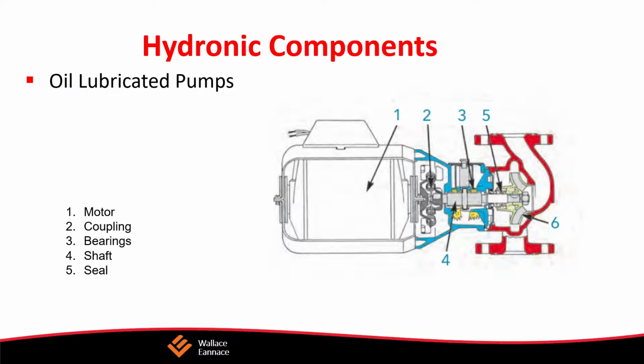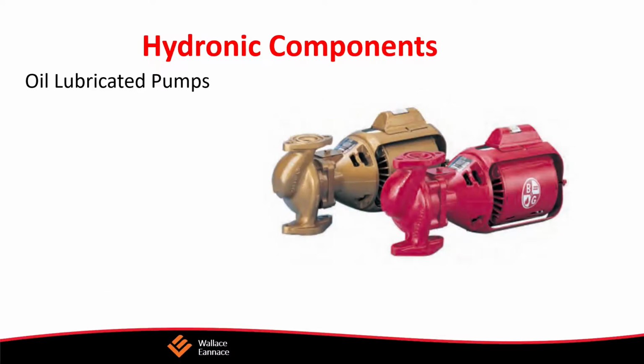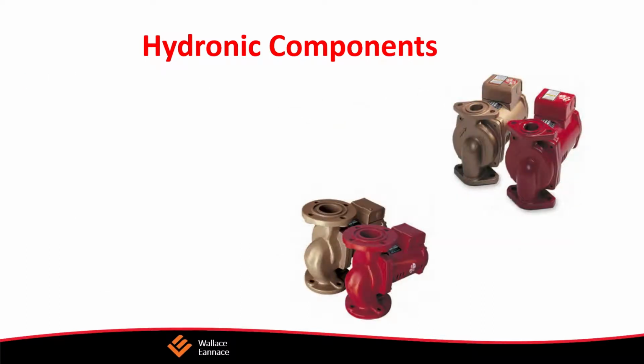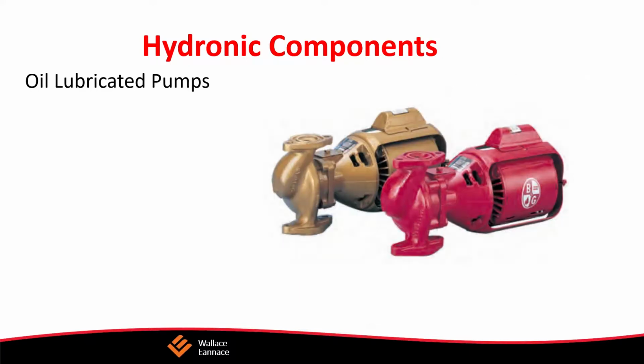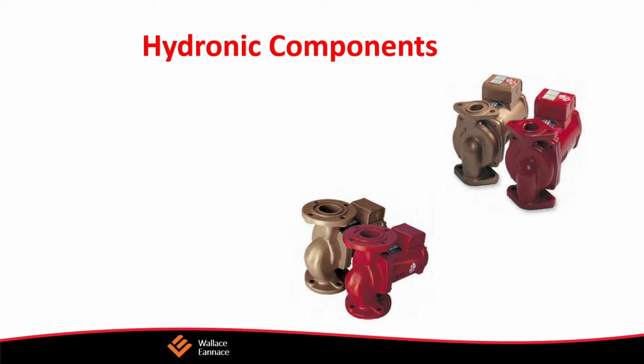Here's a simple example. If we have a zone with 50 feet of 3/4 inch baseboard rated at 160 degrees F, and we have 50 feet of additional piping leading to and from that baseboard, 25 feet one way, 25 feet back, that's a total of 100 feet. So 50 feet times 480 BTUs per foot is 24,000 BTUs. 24,000 BTUs divided by 10,000 is 2.4 GPM. There's our flow.